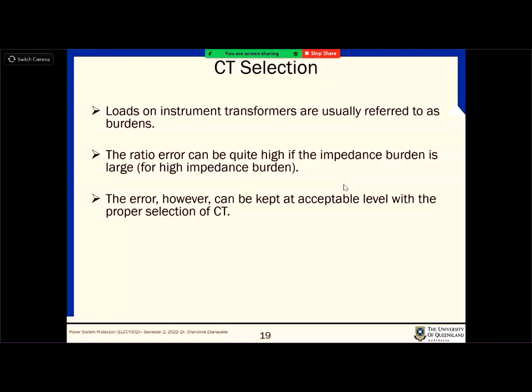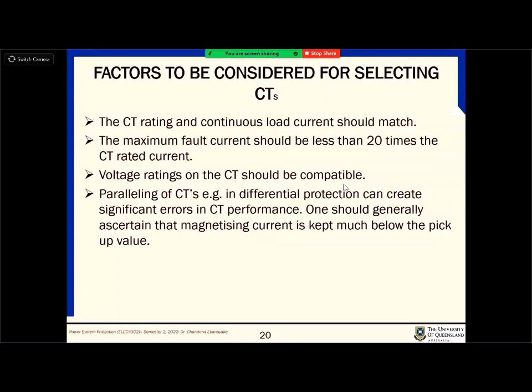When the CTs are selected, loads connected to the CT, as I said, are considered as burden. If the burden, or the relay impedance, is very high, error can be very large. The idea of selecting a proper CT is that we want to keep the error in a limited loop, right? So that is what we do in the CT selections. We will do some calculations of CT selections.